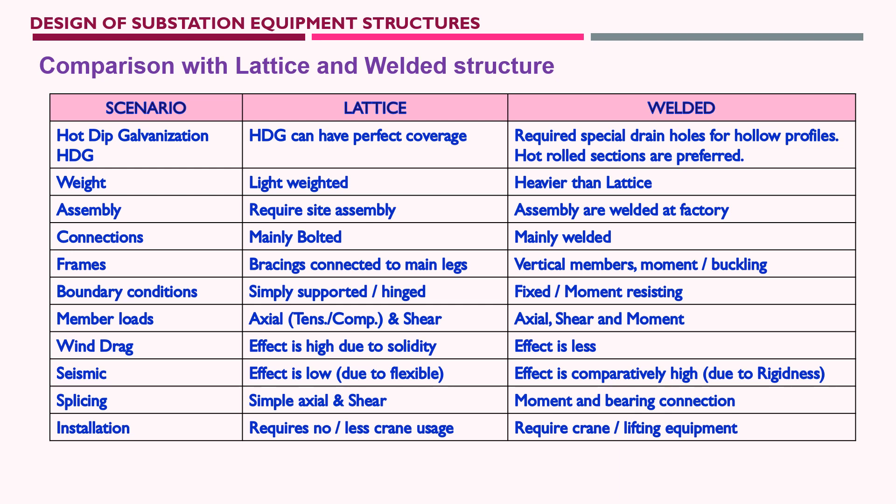For hot-rolled sections like H-sections, UPN, I-beam, or angle sections used in welded structures, hot-dip galvanization is not a problem. Regarding weight, lattice structures are generally lighter than welded assemblies. Site assembly is required for lattice structures, though some projects prefer factory assembly. For welded structures, assembly must be completed at the factory before hot-dip galvanization, so fully assembled welded structures are sent to site after galvanization.